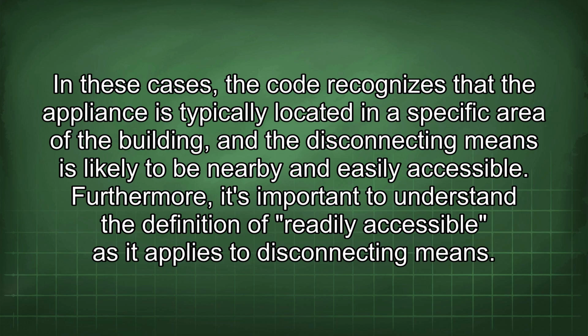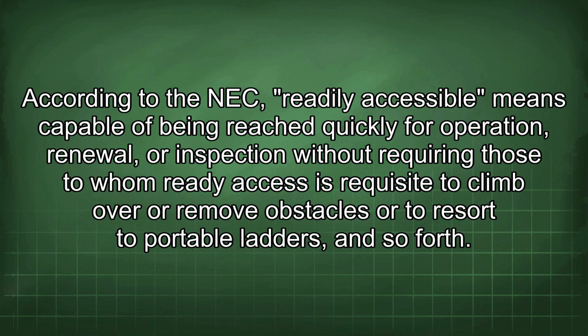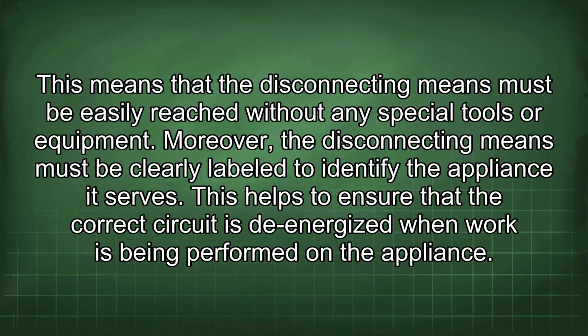Furthermore, it's important to understand the definition of readily accessible as it applies to disconnecting means. According to the NEC, readily accessible means capable of being reached quickly for operation, renewal, or inspection without requiring those to whom ready access is requisite to climb over or remove obstacles or to resort to portable ladders, and so forth. This means that the disconnecting means must be easily reached without any special tools or equipment.